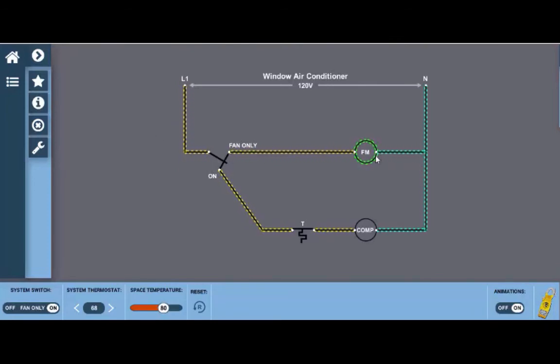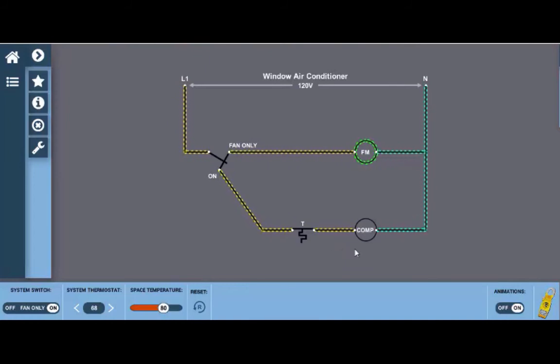We're going to turn the selector switch to the on position and we notice that even though the fan switch is closed to both the fan motor and the compressor and the thermostat's closed, the compressor is not operating. This indicates we have a problem. Now this problem could potentially be in this switch position right here going to the compressor, it could be a faulty thermostat, but we know we've selected the compressor.